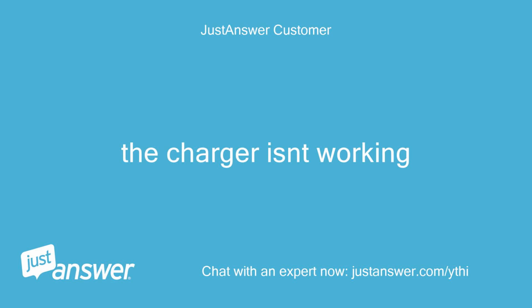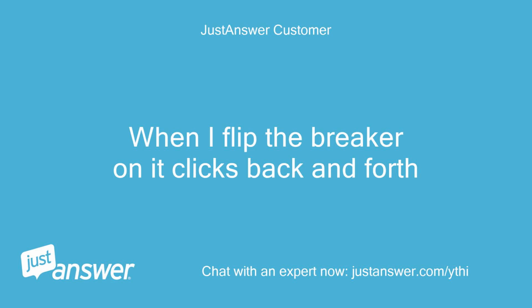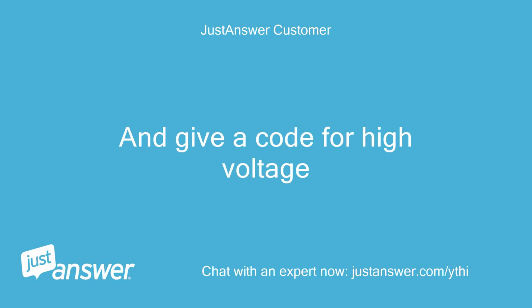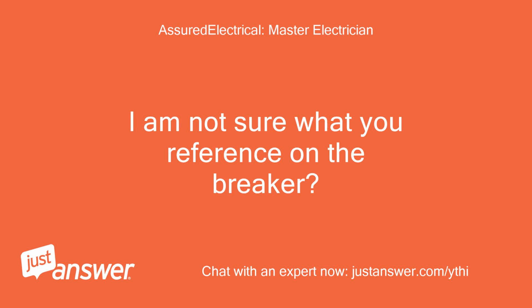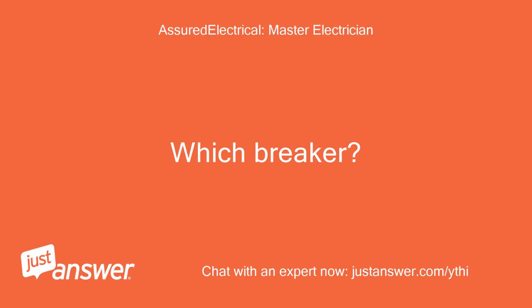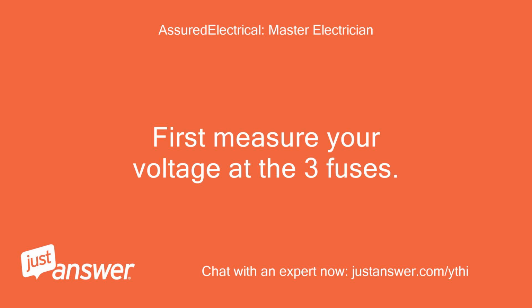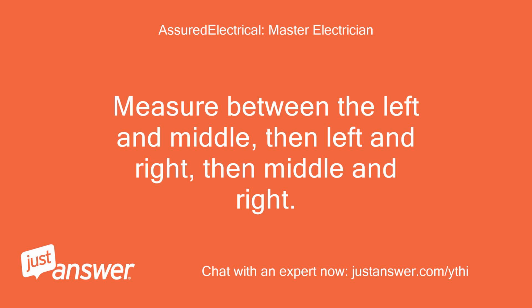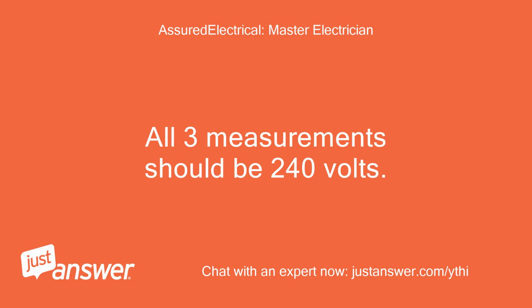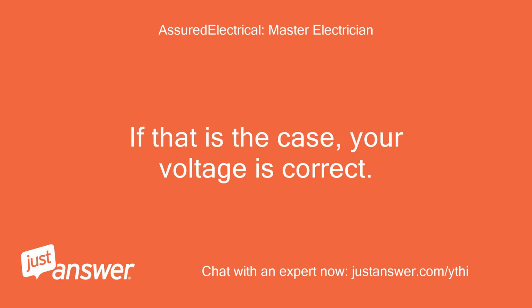The charger isn't working. When I flip the breaker on, it clicks back and forth. And gives a code for high voltage. I am not sure what you reference on the breaker. Which breaker? First measure your voltage at the 3 fuses. Measure between the left and middle, then left and right, then middle and right. All 3 measurements should be 240 volts. If that is the case, your voltage is correct.